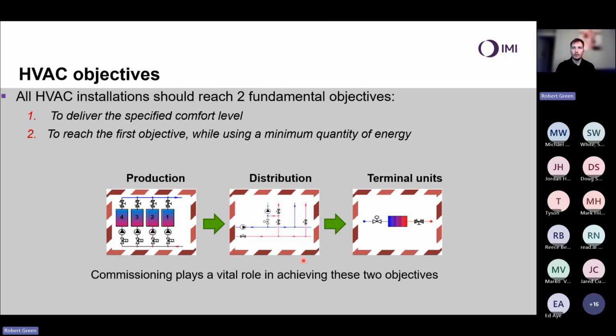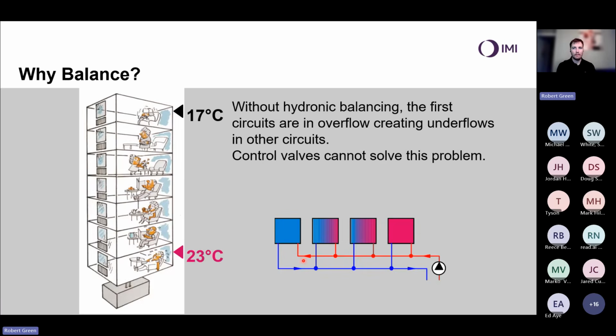And often we can say, well, why do we need to balance? Why should we balance? And let's have a look at a fairly typical building, a high-rise building here. And if we did no balancing at all, water is fundamentally lazy. So without hydronic balancing, what's going to happen? My first circuits closest to the pump are going to be in overflow. And if we have a defined amount of flow in the system, which is a function of the differential pressure this pump is producing, we will end up with underflows in other areas. So the more extreme areas hydronically in the system are going to be in underflow. And underflow is going to cause underheating or undercooling if we're looking at a cooling installation. So we're not going to have a comfortable indoor climate, for number one.